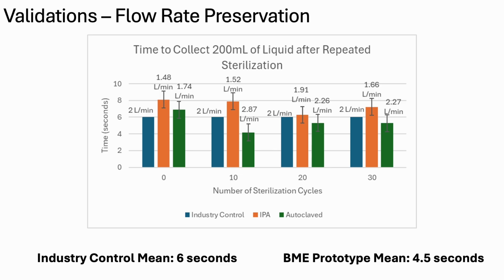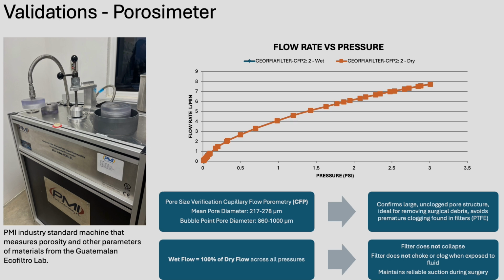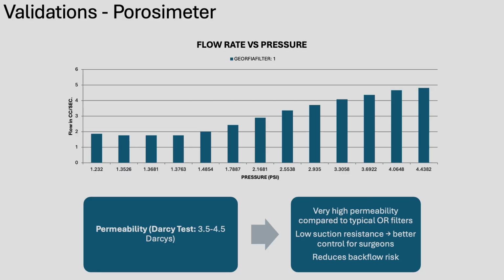For our third validation, we worked with our contacts at Ecofiltro in Guatemala. They used their porosimeter machine to test our unique 2-layer filter design. The results showed that the stainless steel layer helps keep the PTFE from clogging too soon, giving it a longer life. Plus, the permeability test showed a high flow rate with low suction resistance, which is great for surgeons because it means better control and less risk of backflow into the patient.